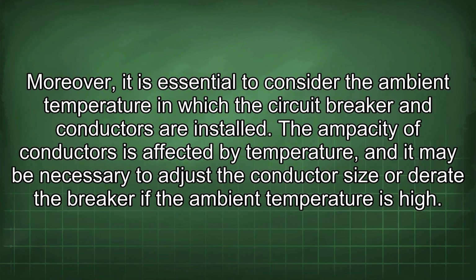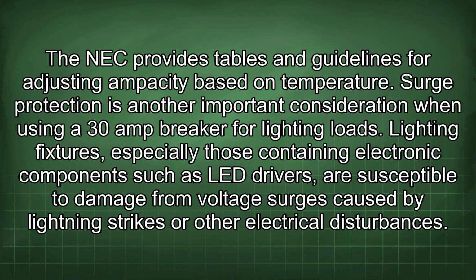Moreover, it is essential to consider the ambient temperature in which the circuit breaker and conductors are installed. The ampacity of conductors is affected by temperature, and it may be necessary to adjust the conductor size or derate the breaker if the ambient temperature is high. The NEC provides tables and guidelines for adjusting ampacity based on temperature.